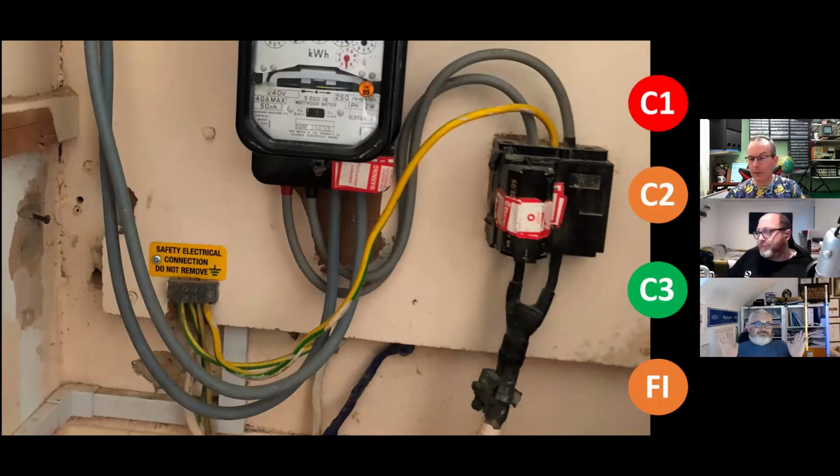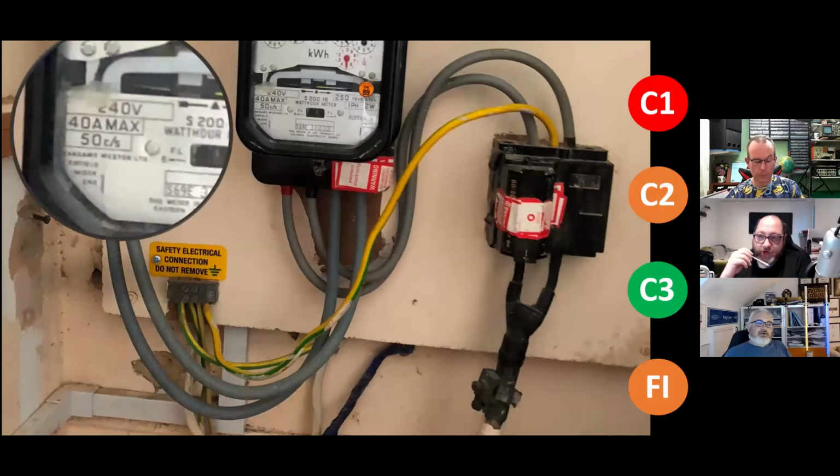What did you do, Paul? Honestly, Gov, when I was doing full-time training and testing, I would have gone, oh, it's a DIY PME. Maybe it's a TNS that's failed, and they've obviously then hooked it in to create an earth that way. That's what I used to call this.